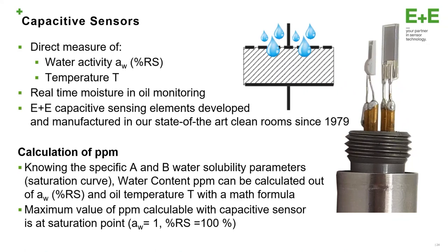This is a real-time moisture monitoring because sensors are placed in state-of-the-art clean rooms. With capacitive sensors, by knowing the specific water solubility parameters A and B, and knowing the saturation curve of the oil, the water content in PPM can be calculated out of the relative saturation using a mathematical formula. The maximum value the capacitive sensors can measure is up to the saturation point — more than the saturation, the sensing element cannot measure.